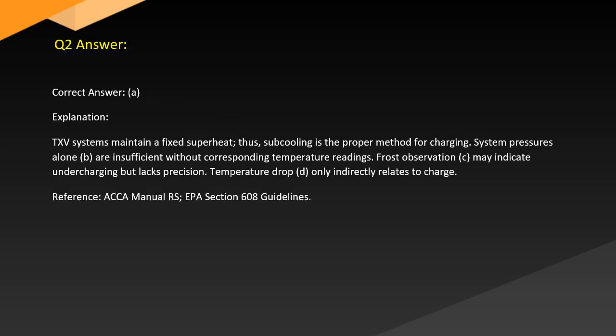Answer. Correct answer: A. Explanation. TXV systems maintain a fixed superheat, thus subcooling is the proper method for charging. System pressures alone, B, are insufficient without corresponding temperature readings. Frost observation, C, may indicate undercharging but lacks precision. Temperature drop, D, only indirectly relates to charge. Reference: ACCA Manual RS, EPA Section 608 Guidelines.